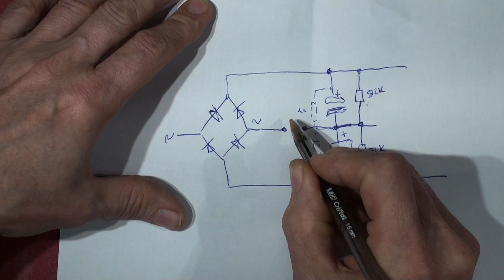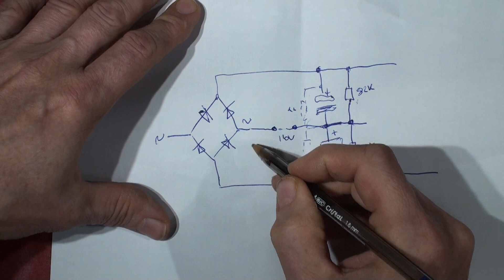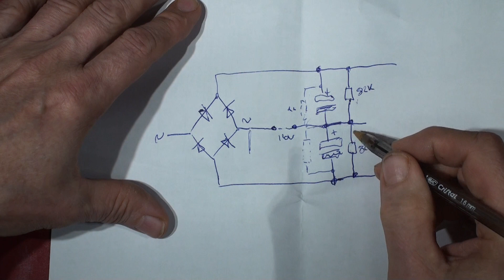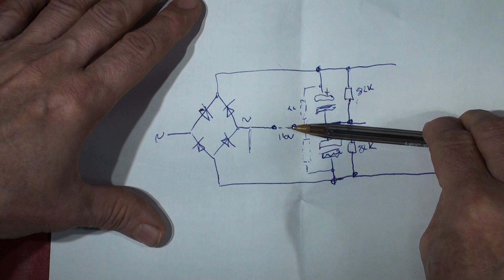So on 110 volts, there's a link in there, okay, in which case this center point voltage is arrested by one of the supply lines. Remember, this is the neutral live supply line there. So on 110, but on 240, if there's any imbalance on this circuit, especially in DC, these voltages will drift out a long way.